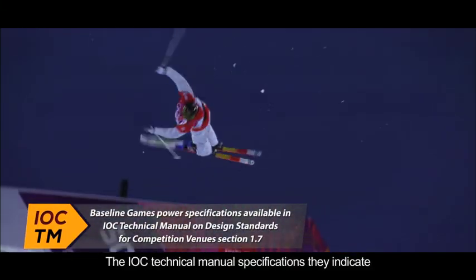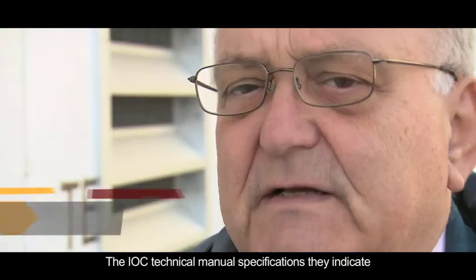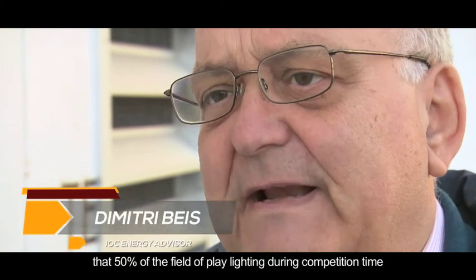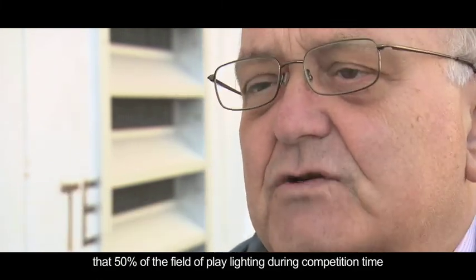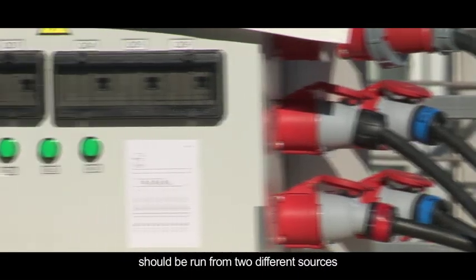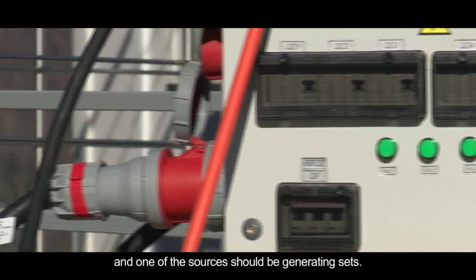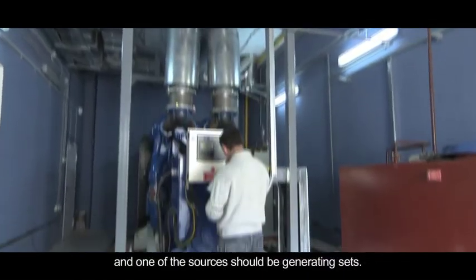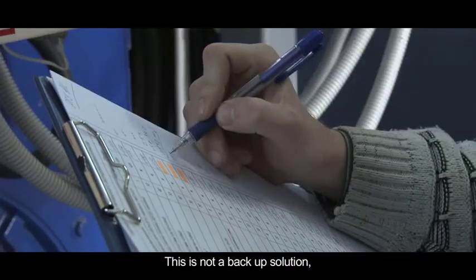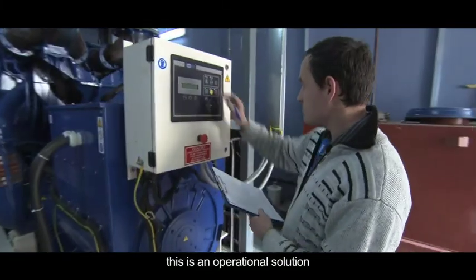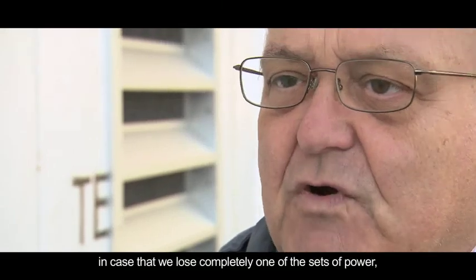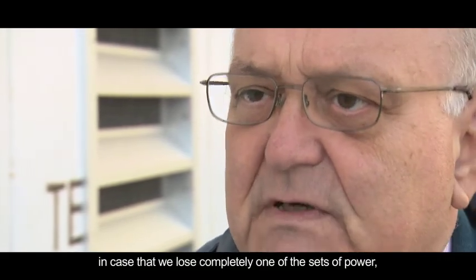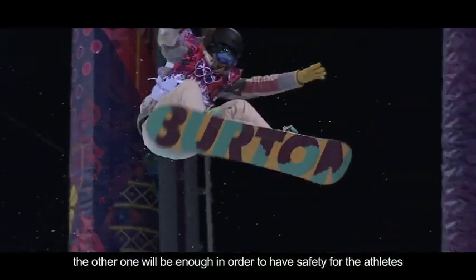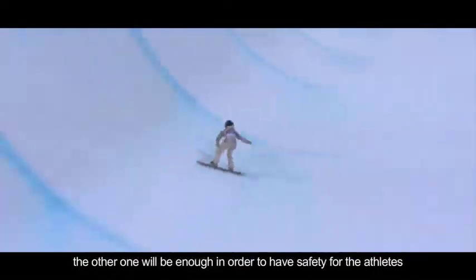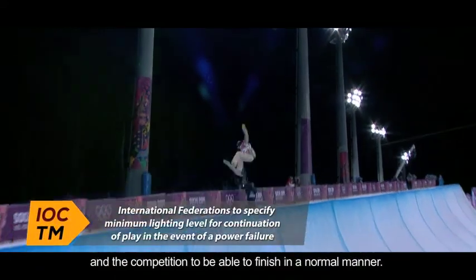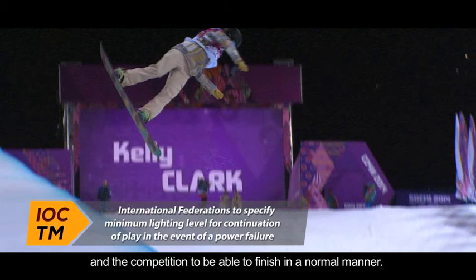The IOC technical manual specifications indicate that 50% of the field of play lighting during competition time should be run from two different sources. And one of the sources should be generating sets. This is not a backup solution, this is an operational solution. In case that we lose completely one of the sets of power, the other one will be enough in order to have safety for the athletes and the competition to be able to finish in a normal manner.